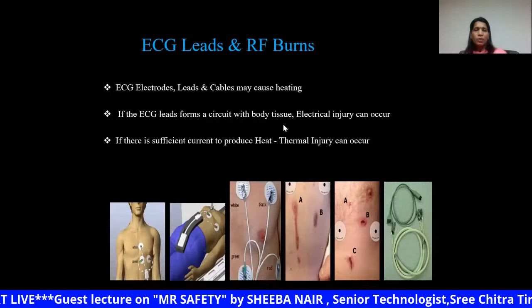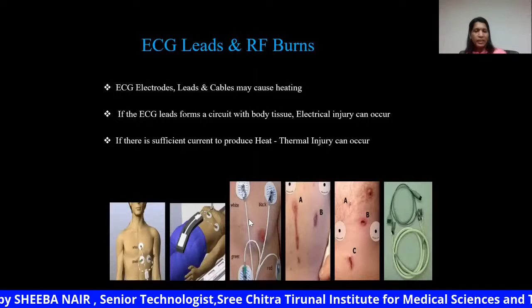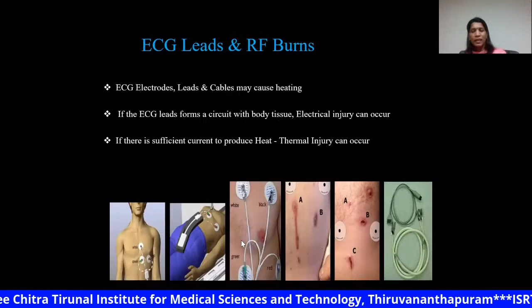The ECG leads we are using can also pose an additional risk of heating if the leads are not insulated, or if the leads are broken, or if they form a closed circuit, they can produce heat. So be very careful while placing these ECG leads. In order to reduce the risk of RF burns, always check whether the cables are insulated. Avoid cable loop formation, and always use MR conditional ECG electrodes and other monitoring devices.